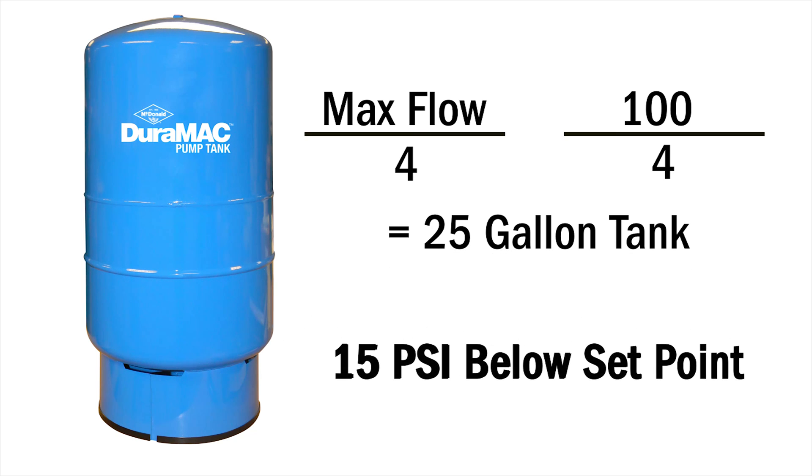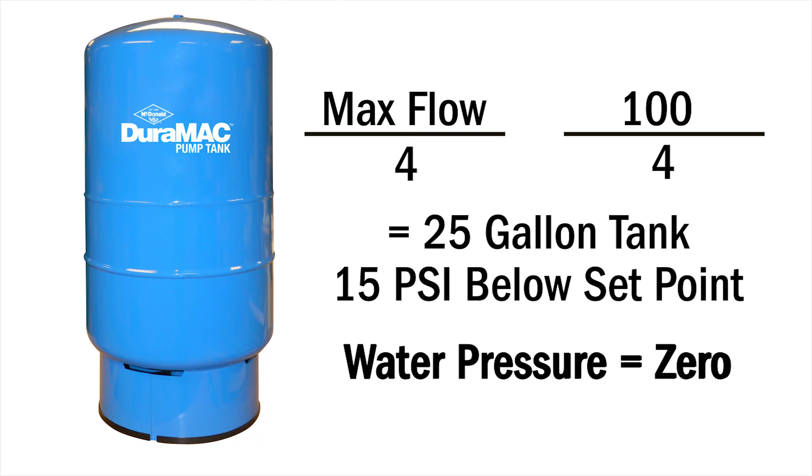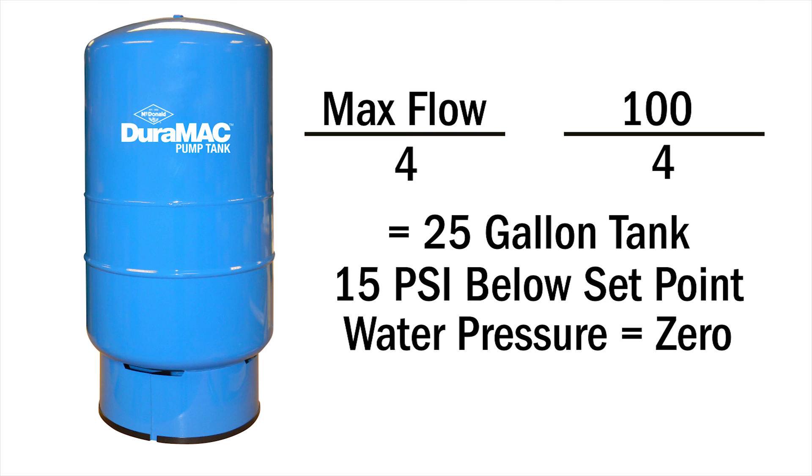The air pressure in the tank will need to be set 15 PSI below the set point. Make sure that the water pressure is zero when changing the air pressure in the tank.